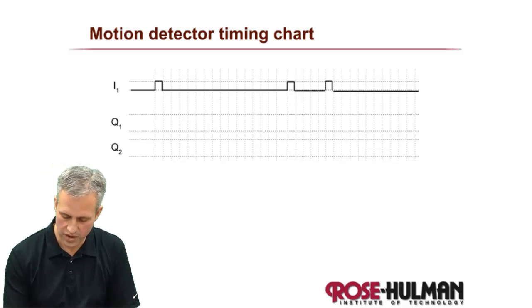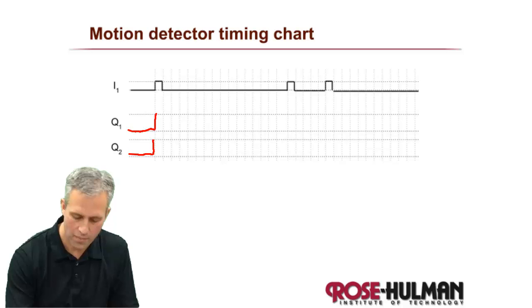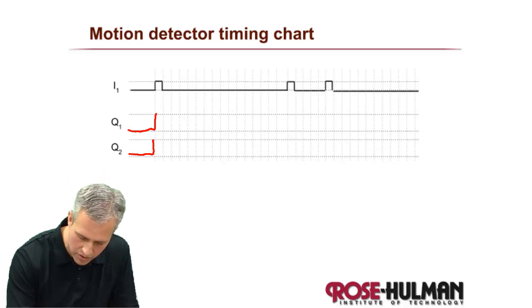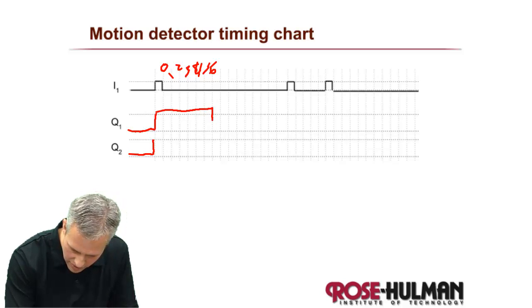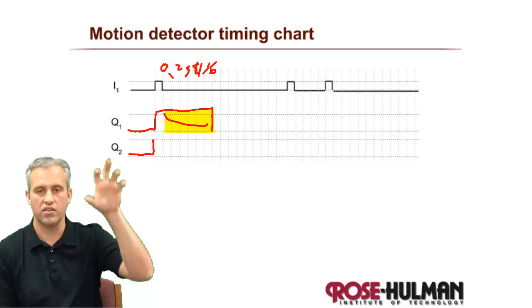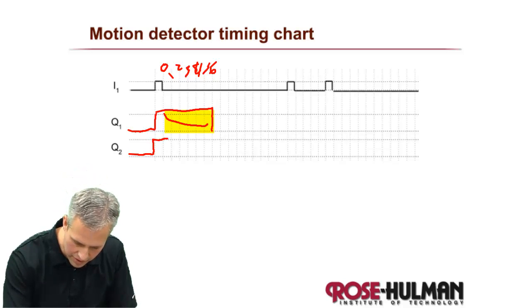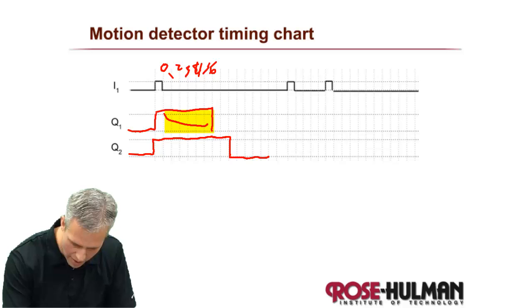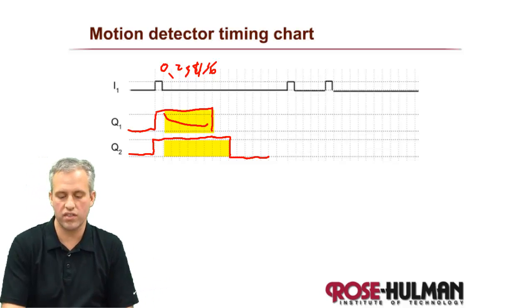Working through the timing chart: both Q outputs start low. As soon as there's motion, they both kick on. When motion stops, you have six seconds until the warning light goes off — that's the off delay. Then you get an additional two seconds beyond that before the main lights go off.